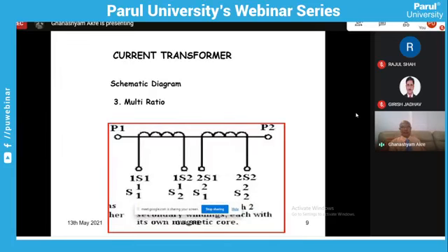Similarly, in the same transformer setup with common primary, here I have shown you the two secondaries, 1S1, 1S2, and 2S1, 2S2. They are two different secondary cores isolated from each other. So they can also have their own ratio. It is not necessary that all of these secondaries will have the same ratio. The beauty of this type of design is that your 1S1, 1S2 can be 100 by 1 ampere, or 2S1, 2S2 can be 200 by 1 ampere. For special purposes, many times you require multiple cores to be connected to the loads and the protection gears at different ratios.